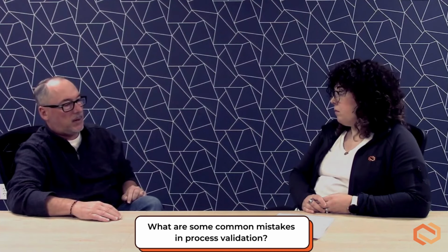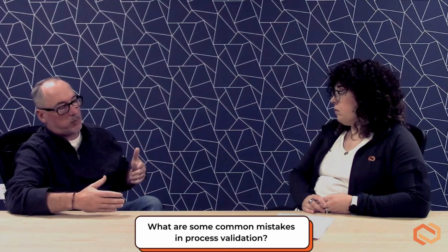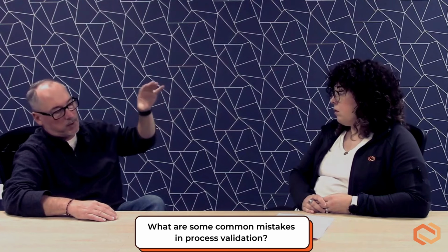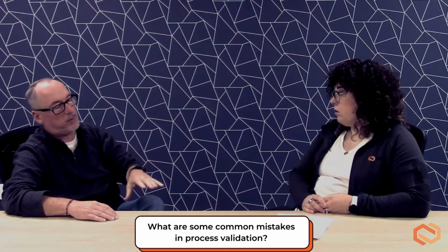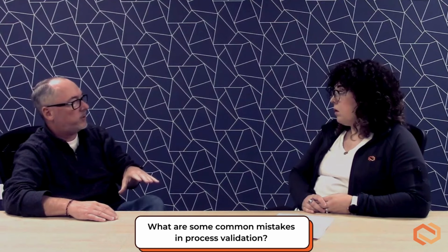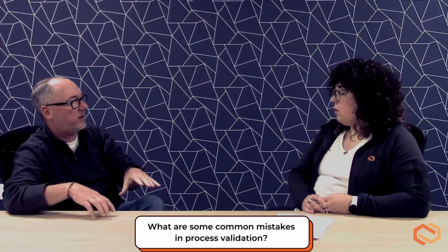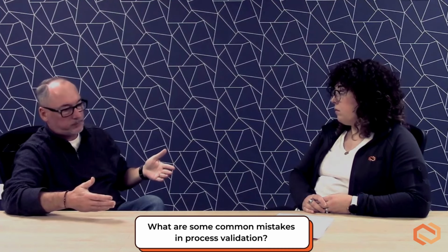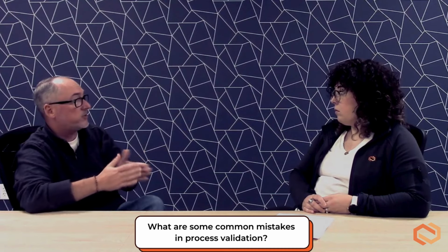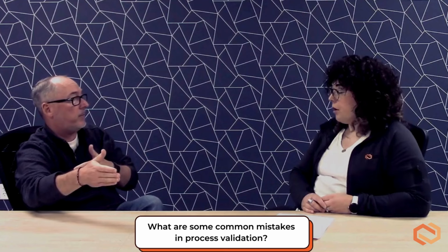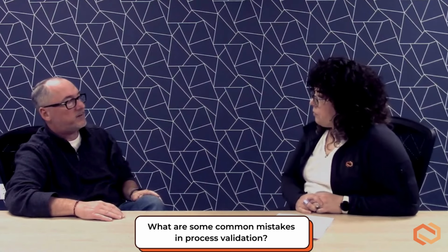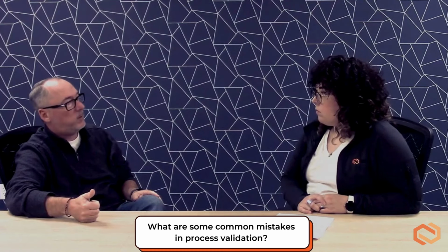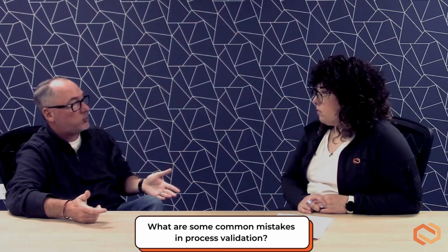Sure. And then, for package validation work, after it's gotten done with process validation and it's gone through ETO or gamma or whatever it's gone through, the inspection of those samples is critical to make sure that sterilization hasn't caused any adverse effects as well. Typically, when samples arrive at DDL, we're expecting them to be pristine, ready to go to the market. And we see a lot of samples in that scenario where the seals are popped, or the seal width is at 1/8 of an inch.